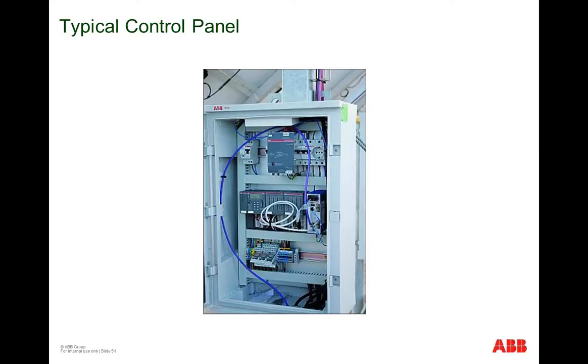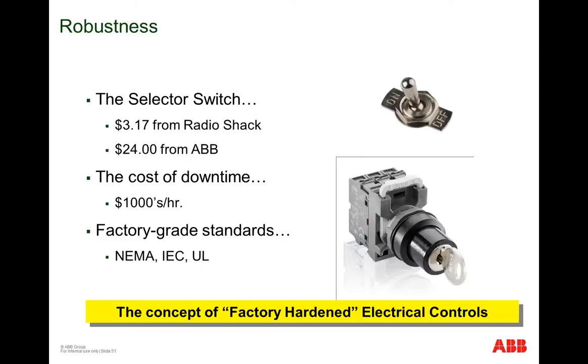Here we see a very typical electrical control panel consisting of a rugged steel enclosure and a back panel upon which are mounted electrical control devices that are interwired to form a system. Wires exit the control box and connect it to operator stations and also to sensors and actuators that are mounted on the machine that we're controlling.